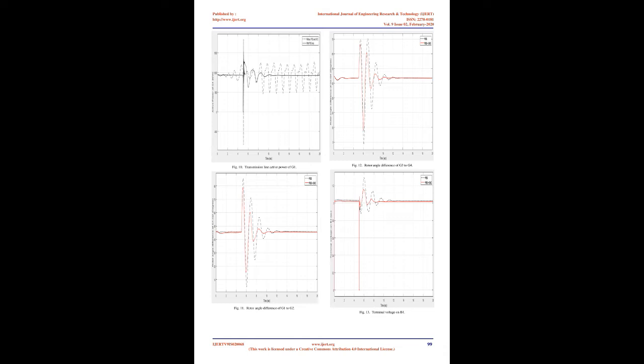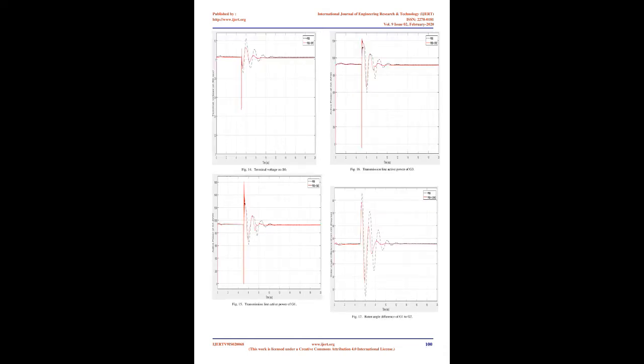A modeling of the SVC. The following assumptions are made in modeling the SVC. First, any harmonic voltage caused by the switching operation of the inverters is excluded from the synthesized AC voltage of the SVC. Second, the instantaneous amplitude of the fundamental component of the AC voltage is proportional to the instantaneous voltage of the DC capacitor. Third, no power loss occurs in the inverters, therefore the active power on the AC side is equal to the active power on the DC side. The assumptions mean that the harmonic voltage caused by fluctuation of the DC voltage is included in the synthesized AC voltage.